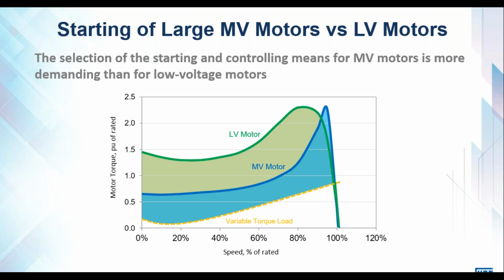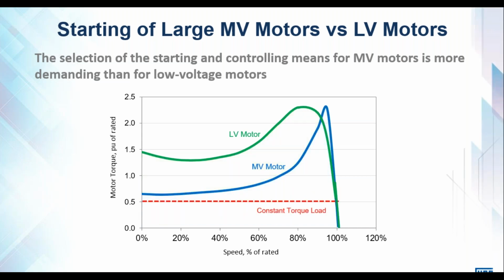However, a medium voltage motor, because of the expense of the material and the expense of a medium voltage machine, we design them a lot closer, or a lot finer, in terms of their application. And so it's much more important to do a specific analysis to make sure that the motor can get the load away. Especially so when we have a constant torque load like a conveyor or a mill, it becomes a lot more imperative to do the starting studies properly.